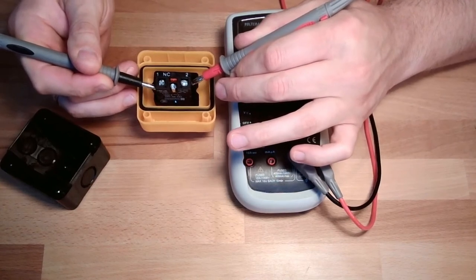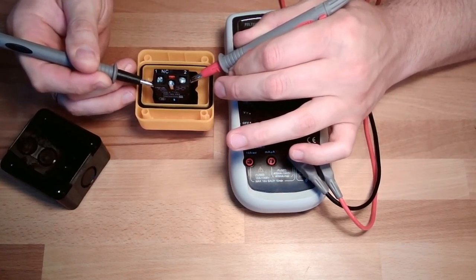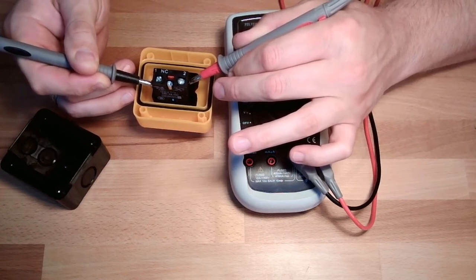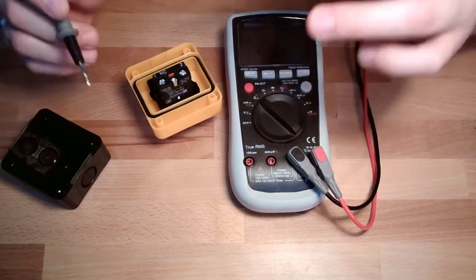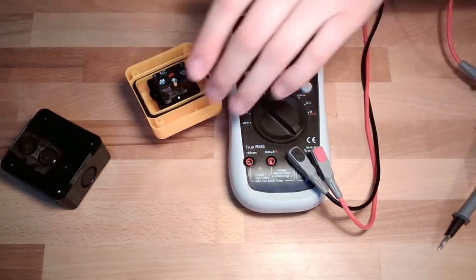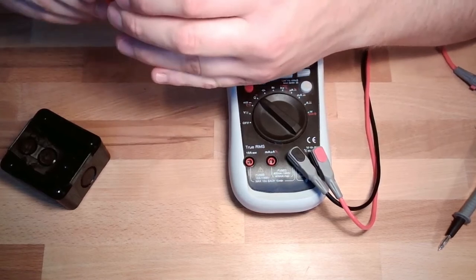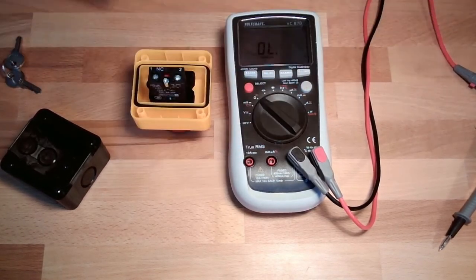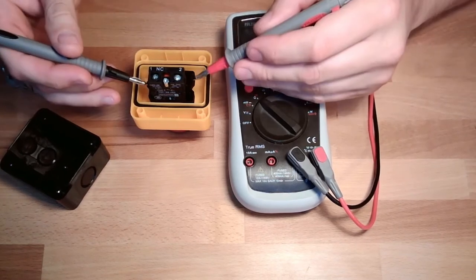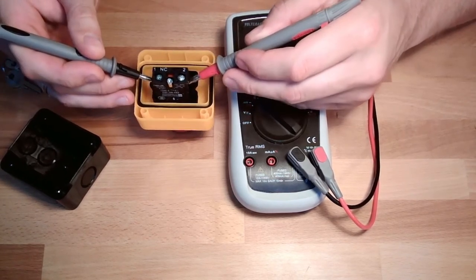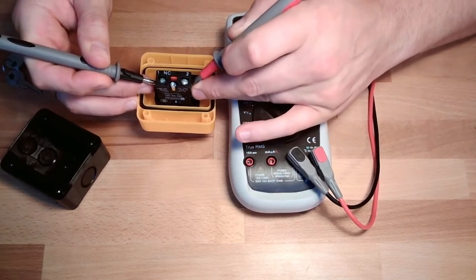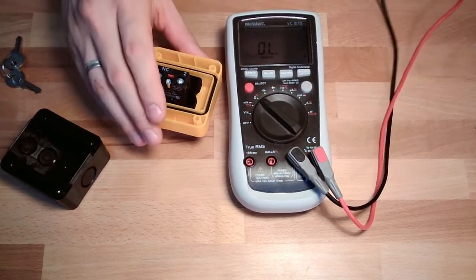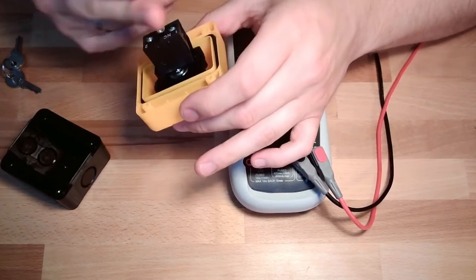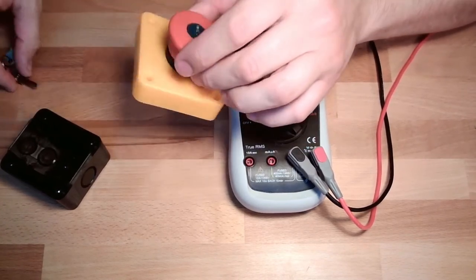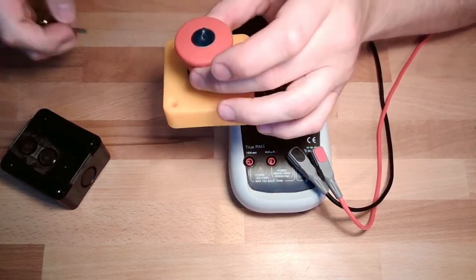In German it would be an Öffner, an opener. Opener you don't say in English. In English it's a normally closed contact. In German it's an Öffner, meaning it opens when operated. Okay, once again: closed, press, open. This is typical for emergency push buttons, because if you have a wire break or something, it would open also. So the standard behavior is closed on an emergency push button.